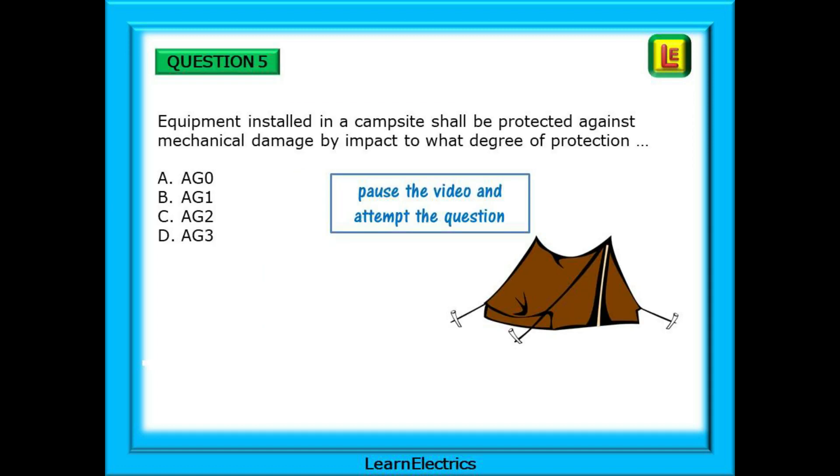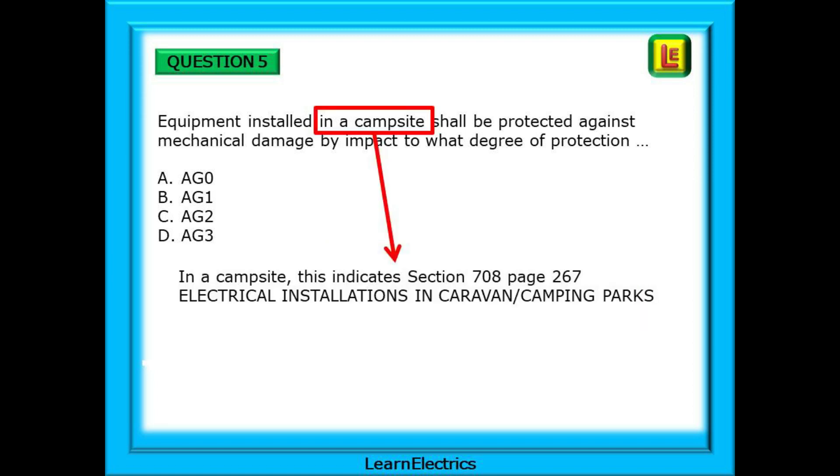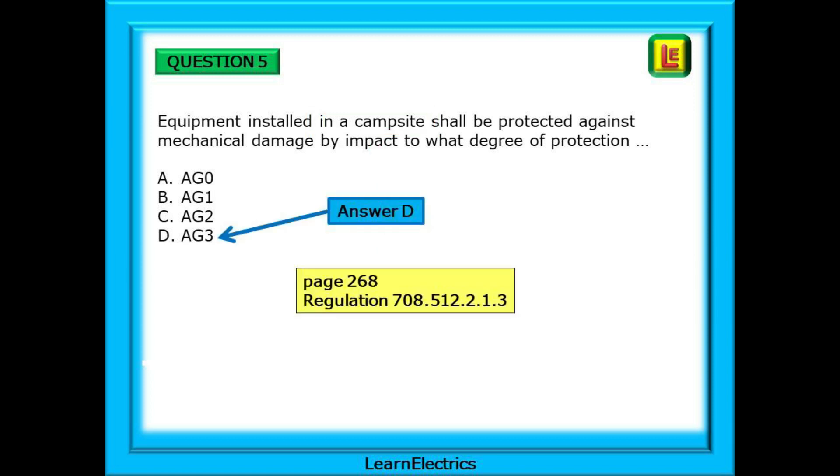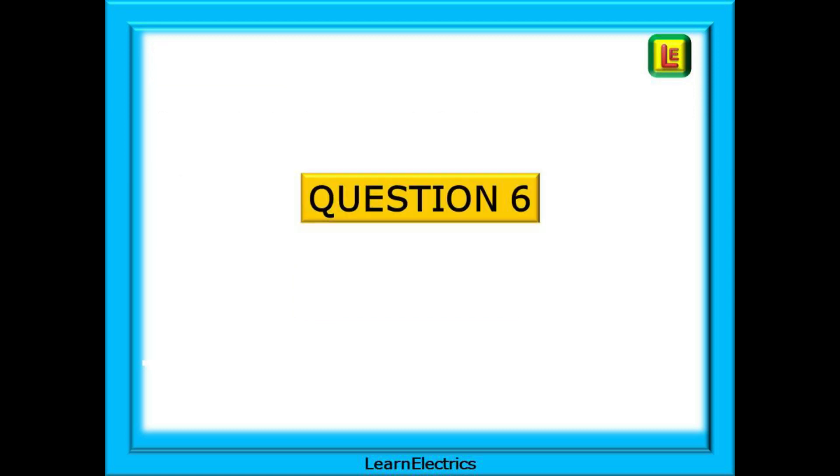Question 5 is next: Equipment installed in a campsite shall be protected against mechanical damage by impact to what degree of protection? Pause the video and have a go yourself. In a campsite, this indicates section 708 on page 267, Electrical installations in caravan and camping parks. So go there now. On page 268 you will find Regulation 708.512.2.1.3 and you should choose Answer D, AG 3.